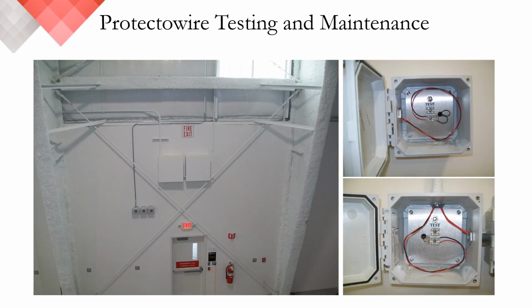This last slide on the topic of testing and maintenance is designed to highlight how you can reduce and simplify testing and inspection time through some creative design and engineering. Here you can see 3 different Protectowire zones have their end-of-line box with a test switch conveniently located just above a standard door. Locating the end-of-line boxes here eliminates the need for any kind of scissor lift. I do want to clarify that the conduit leading to each junction box contains extension cable rather than linear heat detection cable. This prevents 3 different zones from overlapping in such a small space.